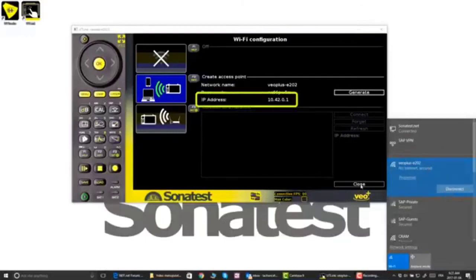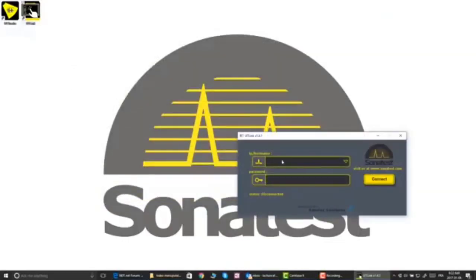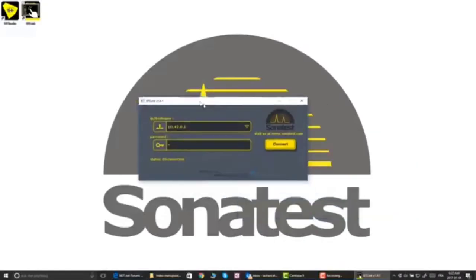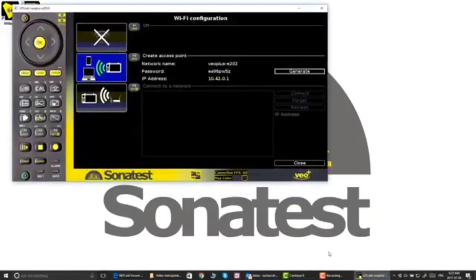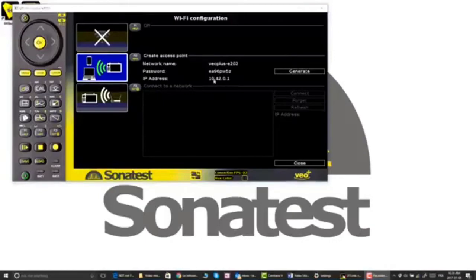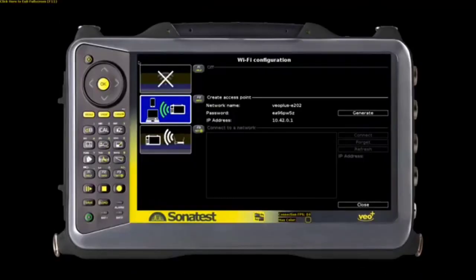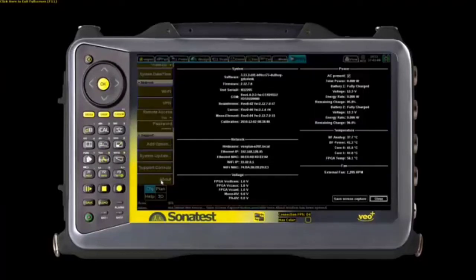Once connected to the hotspot, we can connect our device using the UT-Link with the new IP address that has been generated. At this stage, I enter the new IP address, which is 10.42.0.1, using the same password and simply pressing connect. I have now taken over the control of VEO Plus with this new IP address. We can now validate our connection status in the About window under the Network tab. It is clear to see that the Wi-Fi IP address has been changed to the hotspot address.